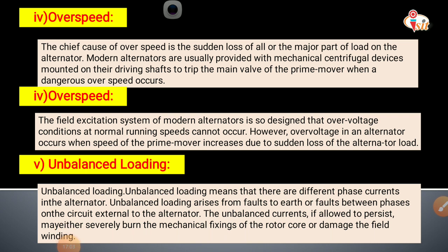The next fault is overspeed. The chief cause of overspeed is the sudden loss of all or a major part of the load on the alternator. Modern alternators are usually provided with mechanical centrifugal devices mounted on their driving shafts to trip the main valve of the prime mover when a dangerous overspeed occurs.